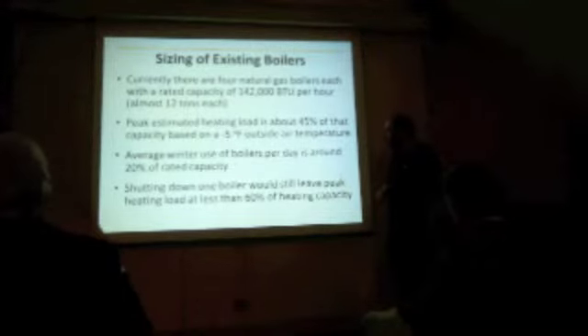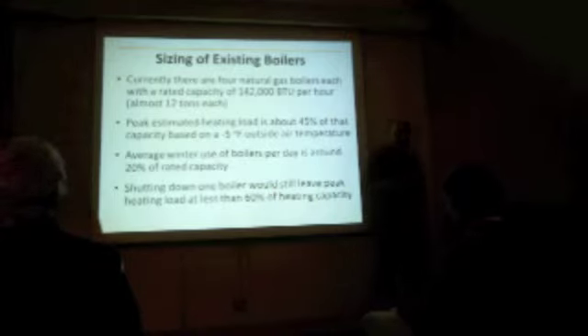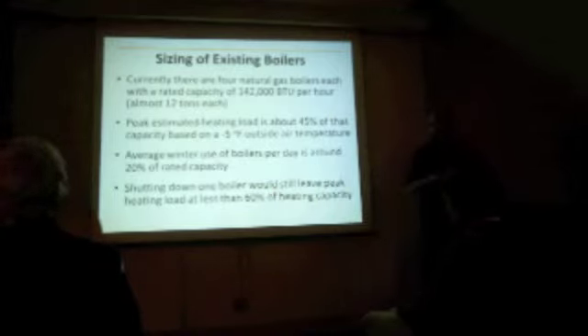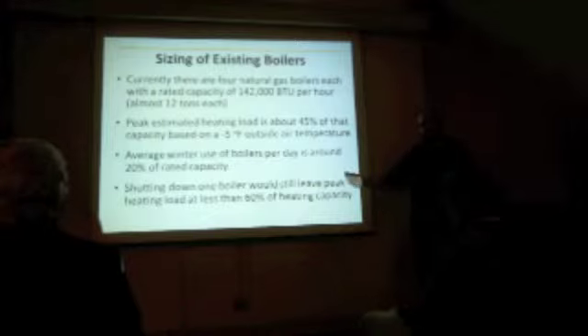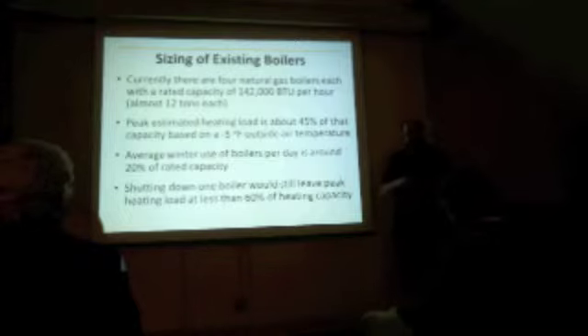And so even with one of those boilers turned off, your coldest day would only get up to about 60% of the capacity of the other 3. And so on a day like today, we really should have seen at least 2 of those boilers cold. And the fact that they're not gives at least one place that you might make some quick improvements for natural gas.